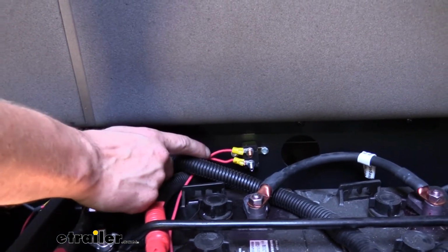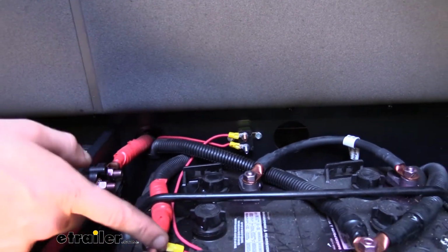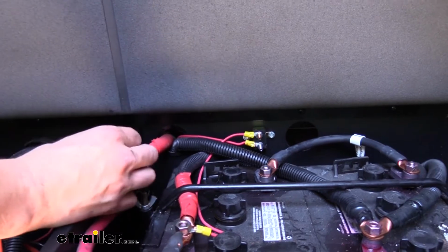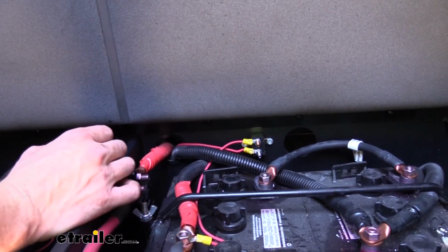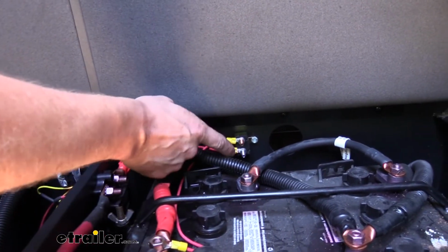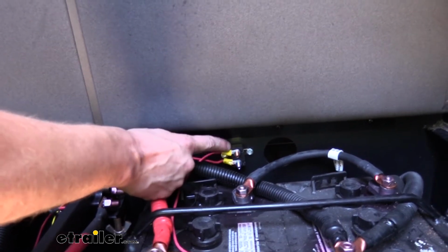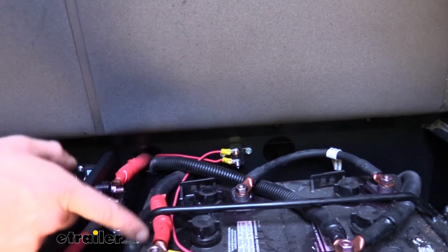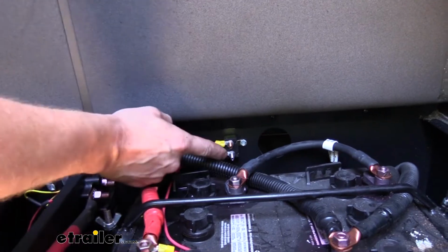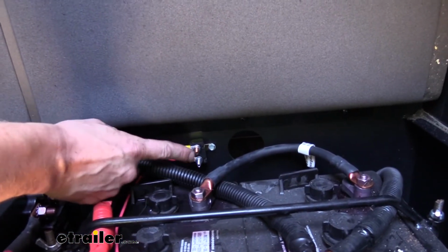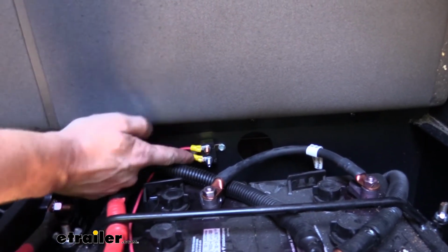We then have two wires we need to run. One's going to run right to the battery here. I recommend you wait to install this one until after you run the other one, so that way the wire isn't live. You'll notice you'll have 3 different ring terminals here. These two on the circuit breaker are going to be the ones that have the smaller hole. The larger hole one is for the battery side. We're going to crimp on the small ones. We can go ahead and connect them to the circuit breaker. Just hold off on the battery side.